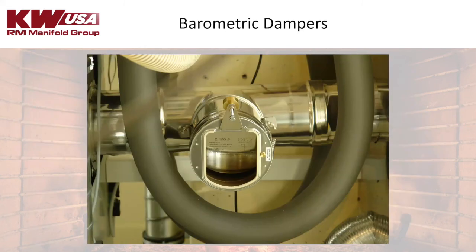And now, what do we do about overdrafting? Draft inducers only create additional draft. So if you're overdrafting, the draft inducer is probably not going to help you much. As we know, draft in your system is constantly changing depending on a number of different factors, which we talked about. So these little barometric draft regulators, also known as barometric dampers, dilute the flue with excess cool air to reduce overdrafting. They automatically react to external conditions to maintain a steady pressure and draft inside the flue gas system.